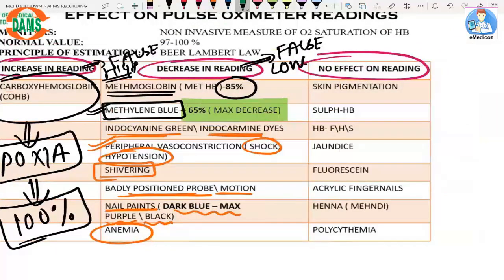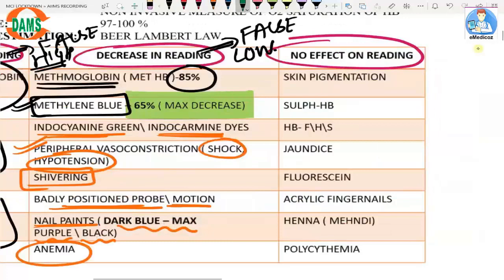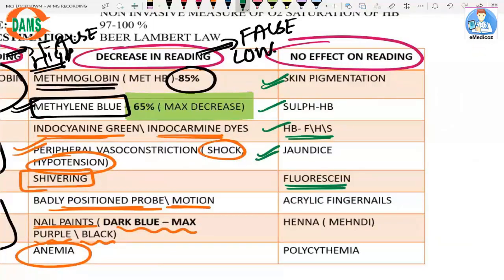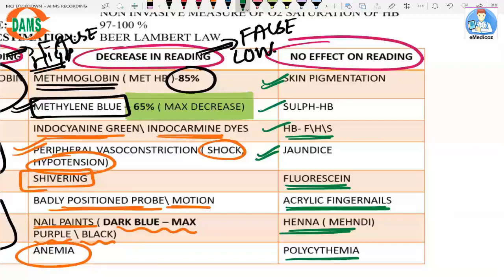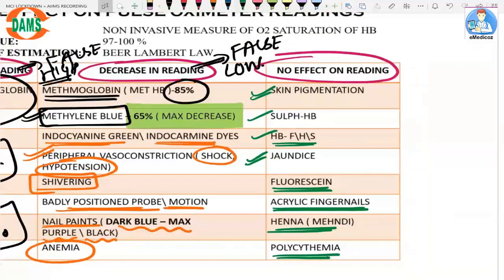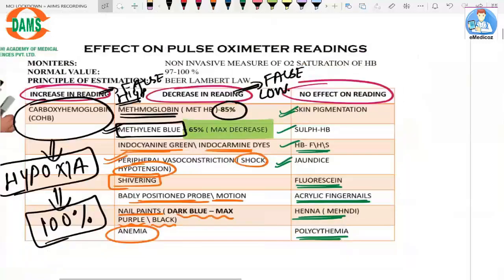Certain conditions would be expected to change readings but actually have no effect: skin pigmentation, different types of hemoglobin such as HbF, HbH, or HbS, jaundice (hyperbilirubinemia), fluorescein dye, acrylic fingernails, henna or mehendi commonly used in India, and polycythemia. All these have no effect on O2 saturation readings.